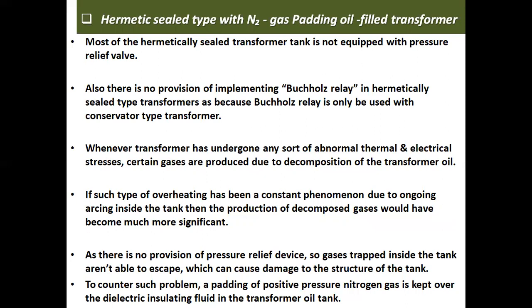Whenever a transformer has undergone any sort of abnormal thermal and electrical stresses, certain gases are produced due to decomposition of transformer oil. If such overheating is a constant phenomenon due to ongoing arcing inside the tank, then the production of decomposed gases would become much more significant. As there is no provision of a pressure relief device, gases trapped inside the tank are not able to escape, which can cause damage to the structure of the tank.